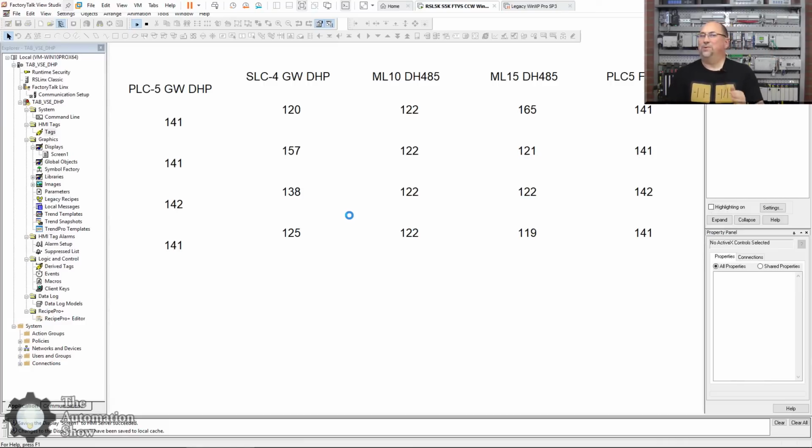So that's why it's important you get that RSLinx topic or shortcut name correctly, or FactoryTalk Linx shortcut correctly. Otherwise, it won't work. And all your tags, I brought in like 50 tags, they all had the wrong shortcut. So I had to change it inside of FactoryTalk Linx to make it match what I imported. Otherwise, I could have deleted all the tags and just re-imported them. But with that, that's how you go about using FactoryTalk View Studio with DF1.